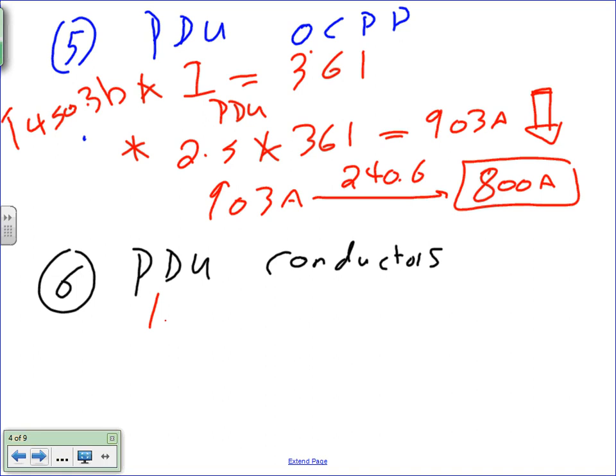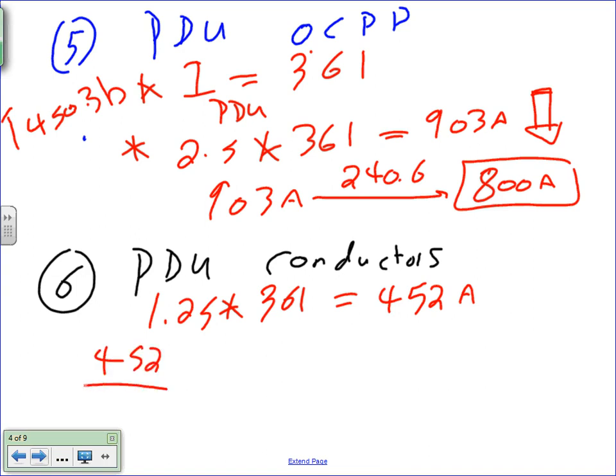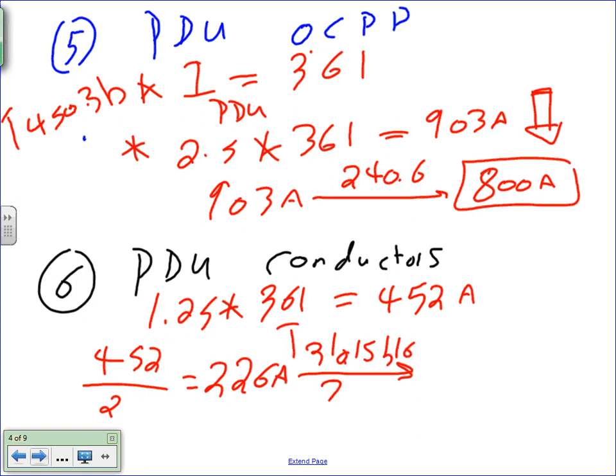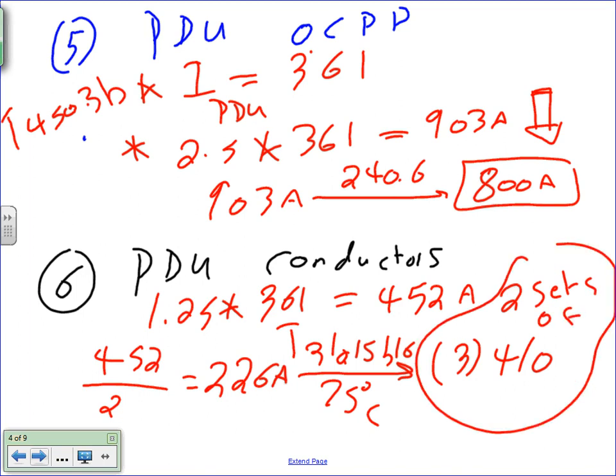Conductors for the PDU, the same thing, guys. 1.25 multiplied by 361, same calculation. 452 amps. And then I'm on the parallel: 452 divided by 2 equals the PDU conductors. Coming to the PDU, if I parallel it, that will get me 226 amps. If you go there, that will get you 310, based on 310.15(B)(16), 75-degree column. That will get you 3 conductors, number 4/0. And how many sets? Two sets of 3 conductors, number 4/0.